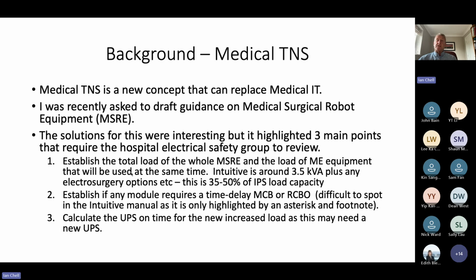And the reason for this is that the basic Da Vinci robot has got a 3.5 kVA load requirement. And if you start buying electrosurgery options, it can get up to 50% of the IPS load capacity. So if you've got medical devices that add up to about 4 kVA, you're right close to the load of the IPS. So that's the first job. And I don't think people are doing that.